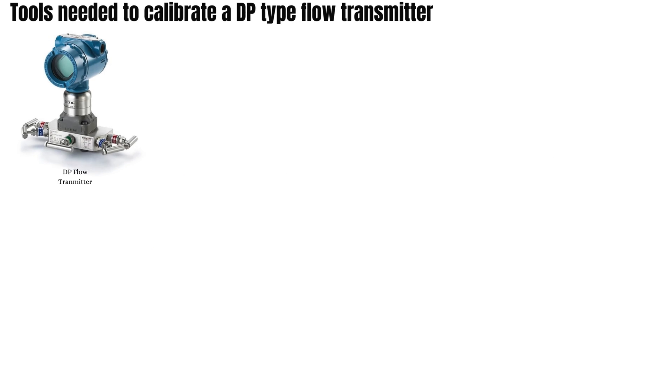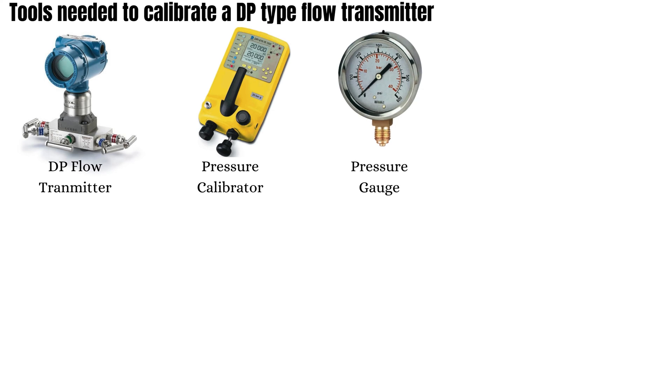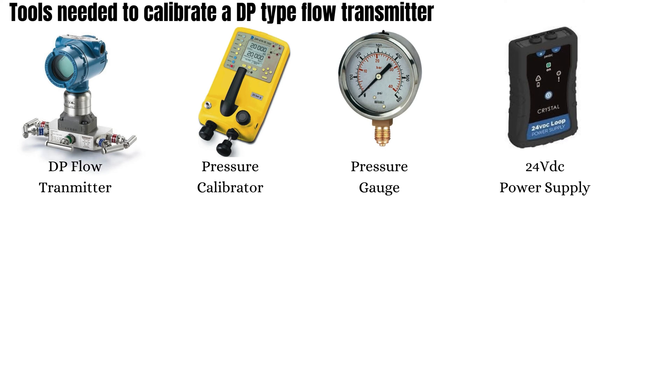What are the tools needed to calibrate a DP type flow transmitter? Besides the DP flow transmitter itself, we will need the below mentioned tools to perform a calibration: a calibrated pressure calibrator capable of indicating pressure in mmH2O, because here the DP transmitter for measuring flow has a range in mmH2O; a calibrated pressure gauge of the appropriate range; and a 24 VDC power supply if the pressure transmitter is not connected to the system and needs an external power supply.